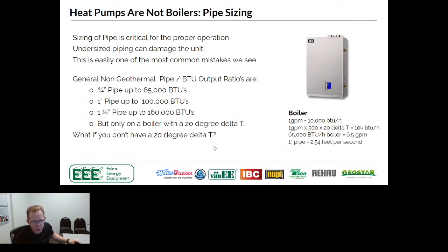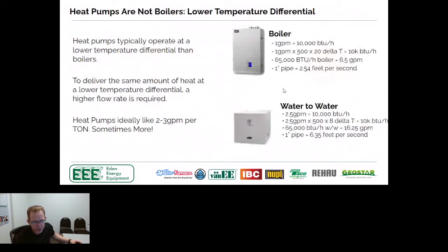Well, where this goes wrong on the hydronic heat pumps is the assumption that we're working on a 20-degree delta T. So what I've done here is I've reworked the math, in this case with a water-to-water unit, but the principle applies the same with an air-to-water unit. Water-to-water and air-to-water units do not work on a 20-degree delta T. You cannot get most residential air-to-water and water-to-water equipment to run on a 20-degree delta T because they are designed completely differently from an efficiency standpoint. If we took the time to read the manufacturer's manual, we would find out that they typically would like to have somewhere in the 2 to 3 gallons per minute per ton.